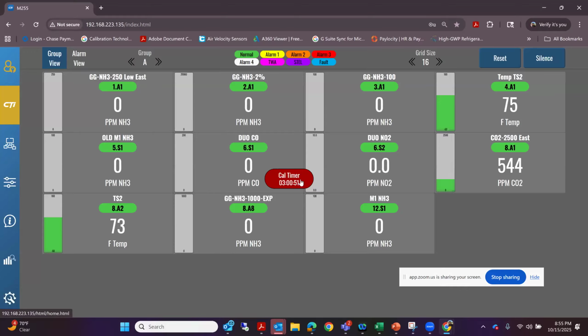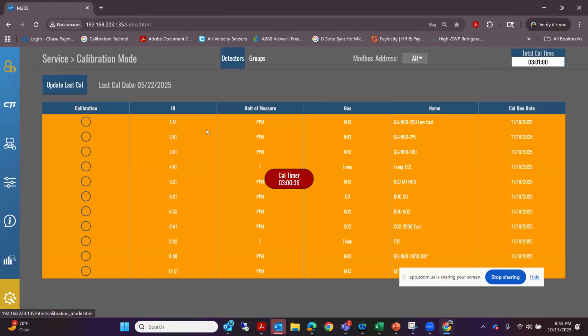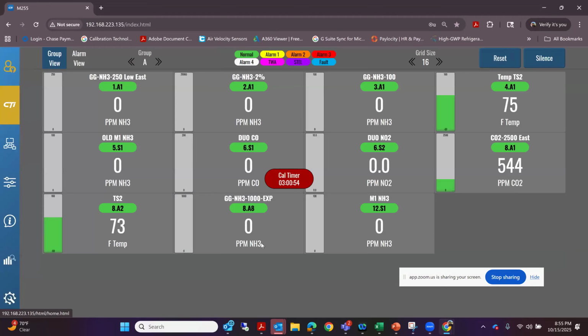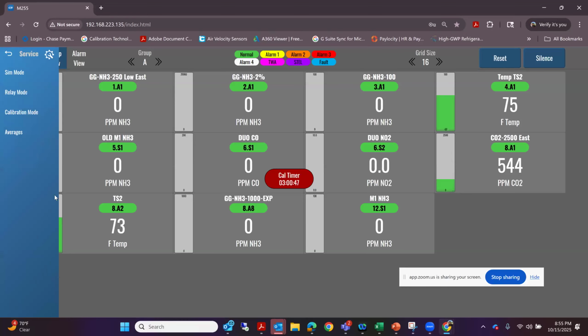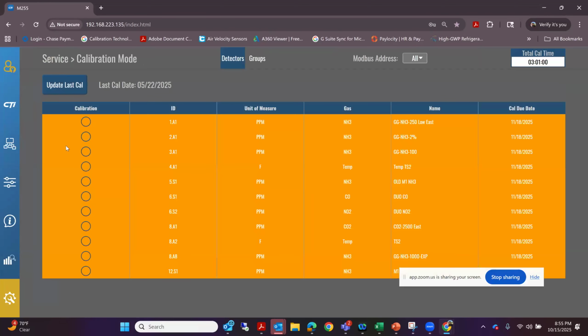And that's pretty handy, because it's going to time out and never leave you vulnerable on your system, which can happen if somebody forgets to go back and take the calibration mode off, or if it doesn't time out on its own. So that's a safety feature that we wanted to put in there. And we also wanted to put in not only groups of sensors, but we also thought, well, what about the guys that just want to calibrate all their compressor room sensors, but not that high level sensor, not that 0 to 20,000? So we can go ahead and take it offline for a few hours. We can go calibrate everything else, and we'll know that we're not going to accidentally shunt trip ourselves and disrupt operations and get in trouble. So we tried to throw everything we could in here that made sense, to make it really helpful. And then once everything's calibrated, you can highlight and update the calibration on all your sensors here automatically.